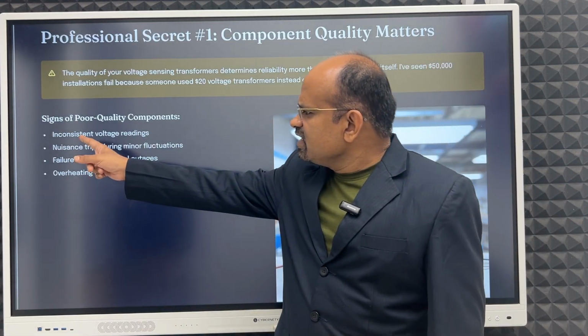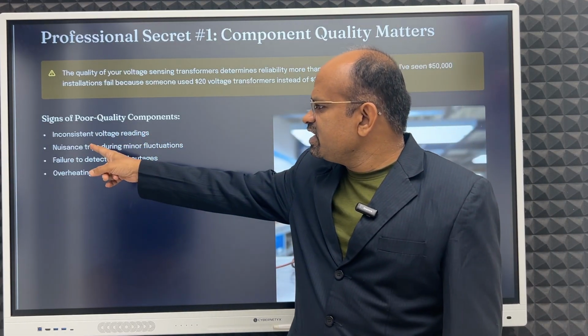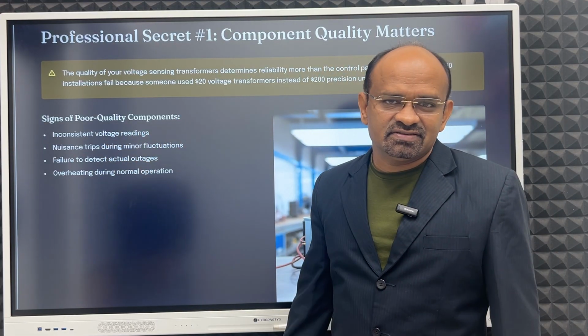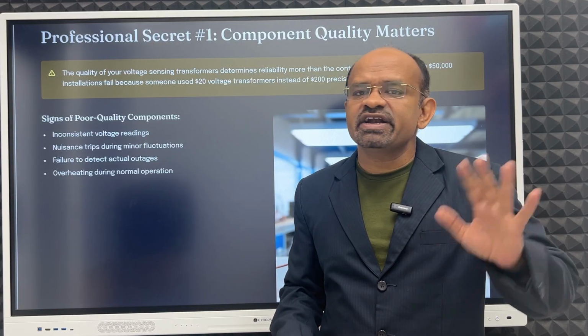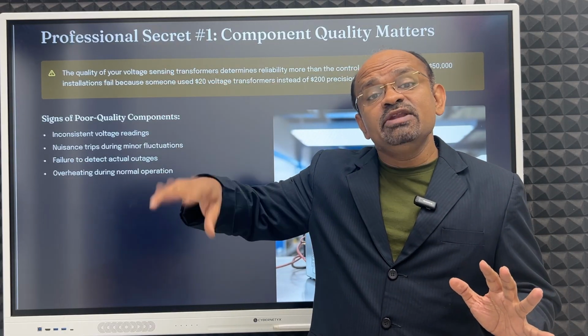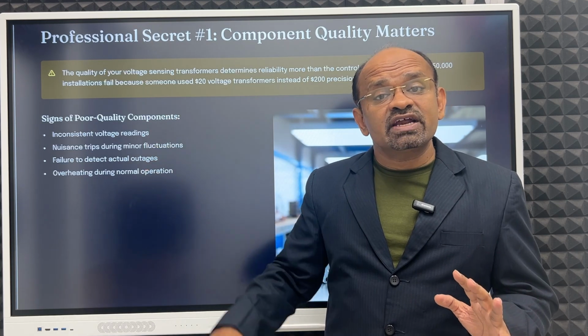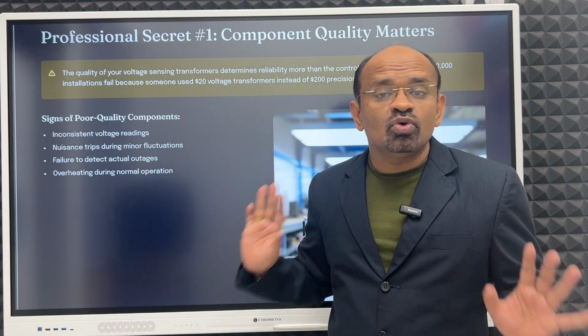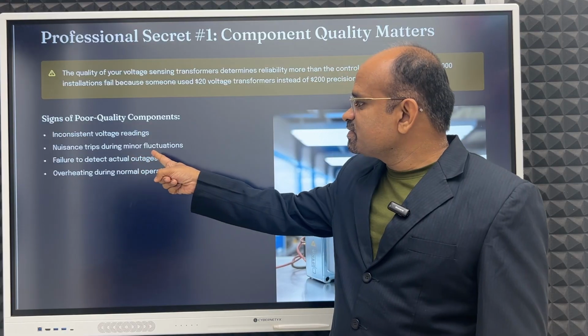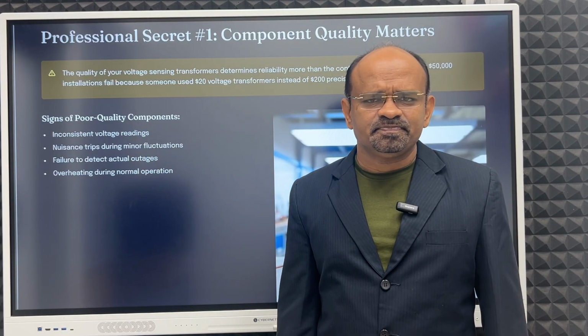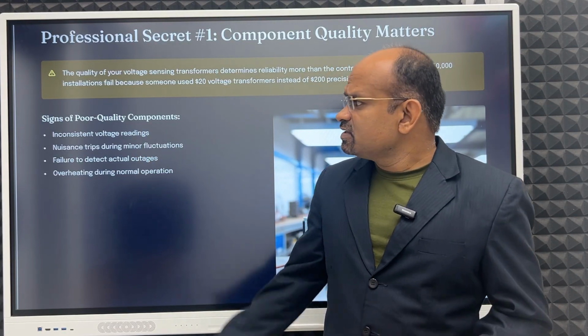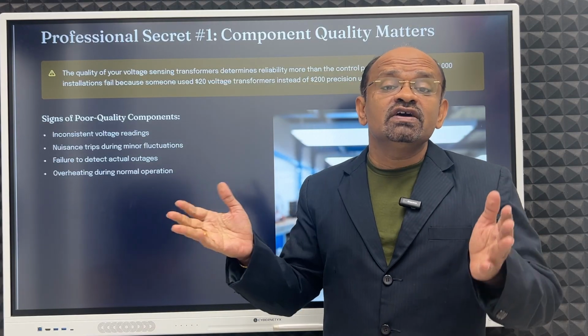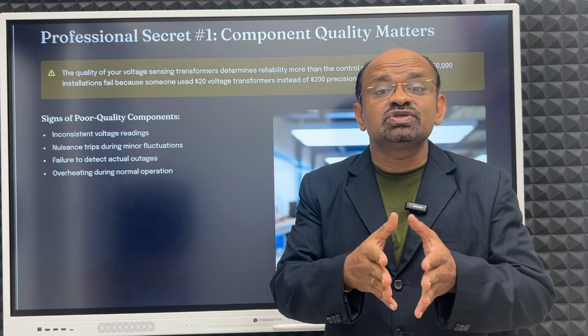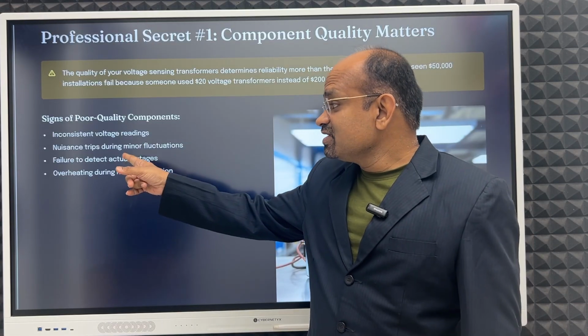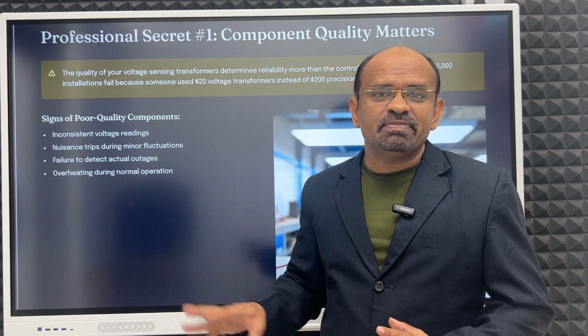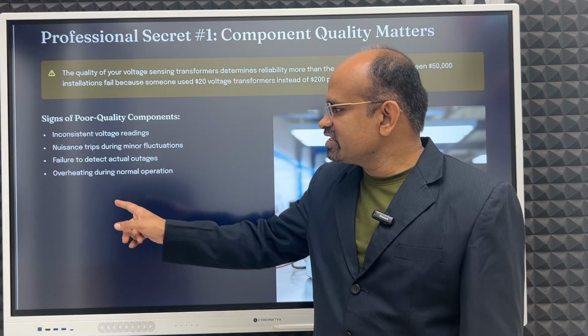Okay. Then signs of poor quality component: inconsistent voltage readings. It is not giving consistent, proper readings. Though the input EB power or city power is stable, still it is not giving the proper voltage. Then nuisance trips during minor fluctuations. It will trip the contactor. It will give the command to contactors or switching devices. So this is very important, otherwise nuisance tripping will happen. Without reason it will trip, that is nuisance tripping.